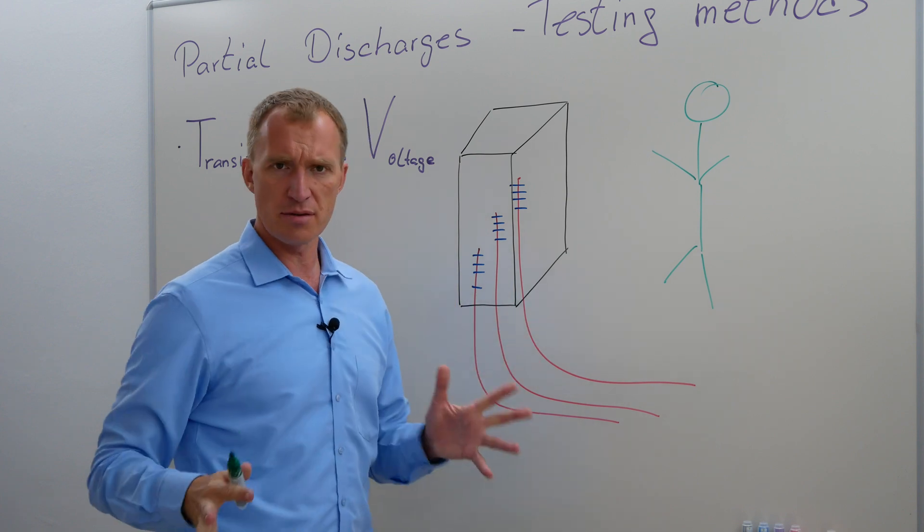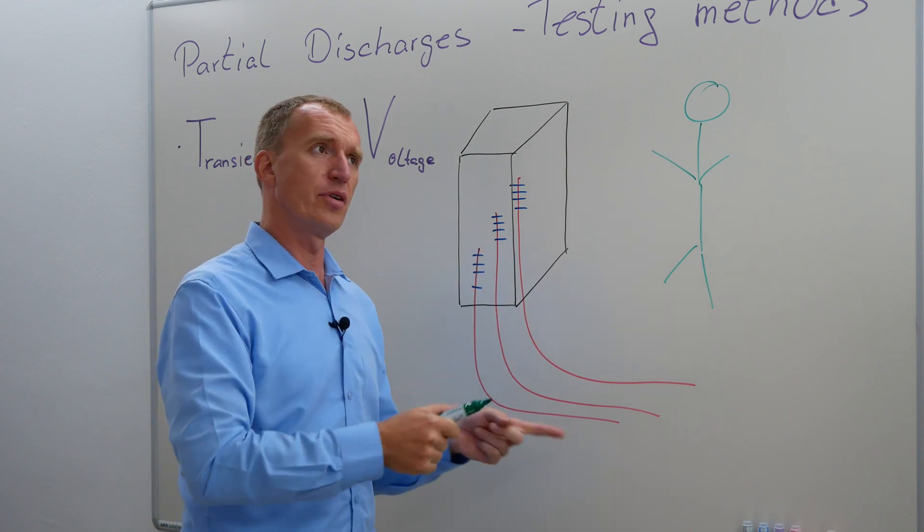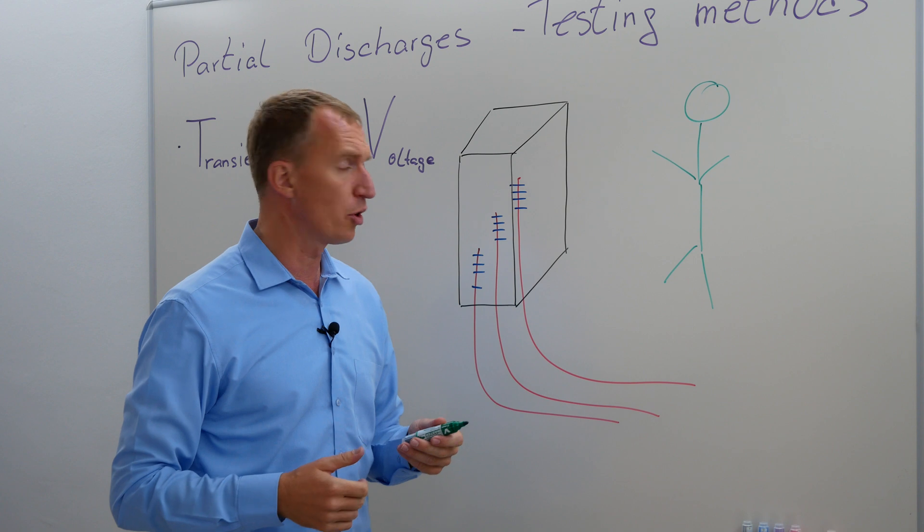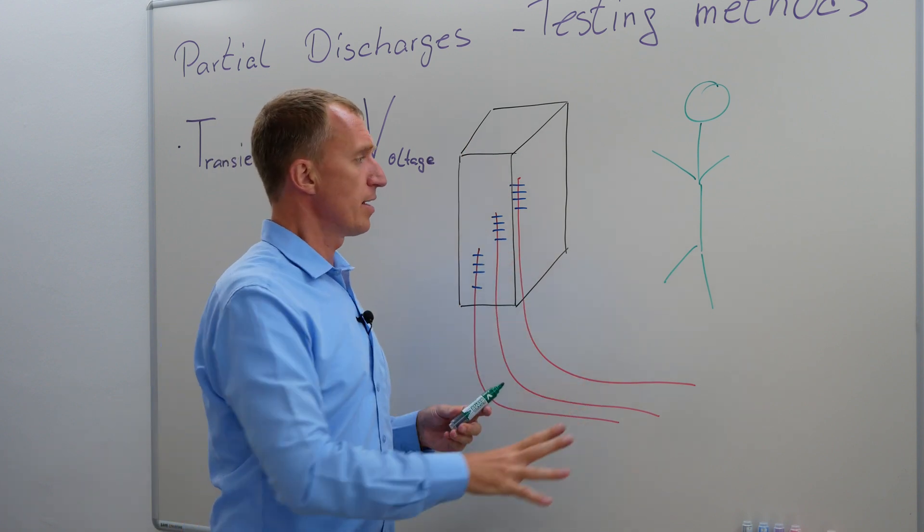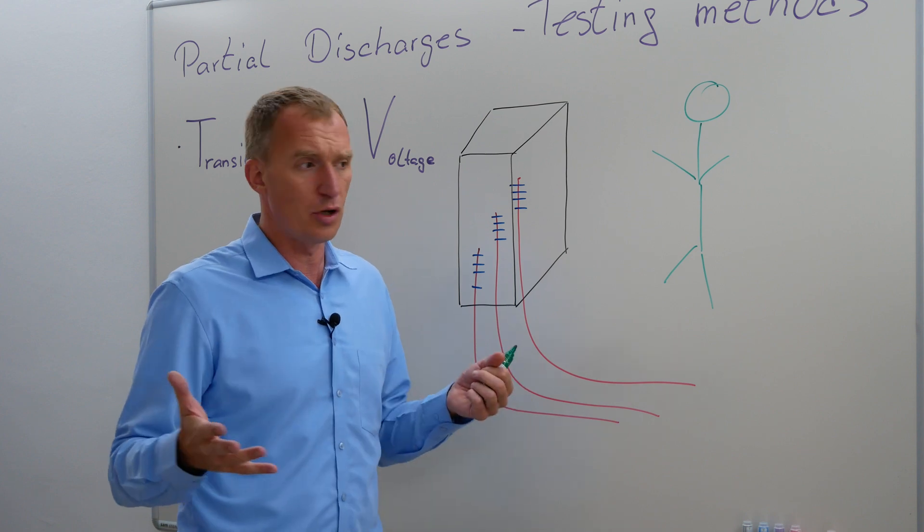It would be really cool to know if there's partial discharge inside or not. There are certain reasons why partial discharge could be interesting because there are very rare cases where this actually triggered an explosion if there's too much oxygen going in there. But let's say for now I want to know are there partial discharges or not, because if there are, maybe I don't want to open it.